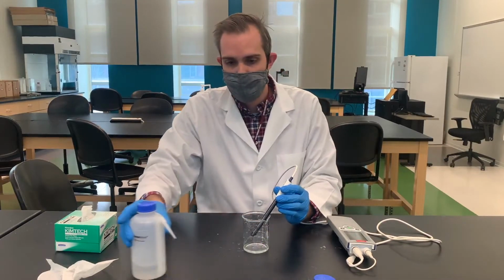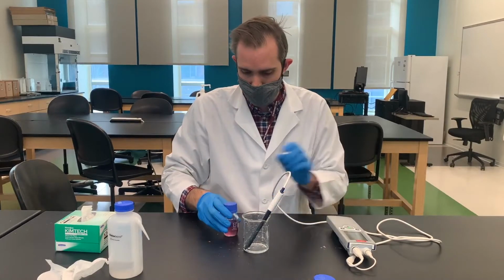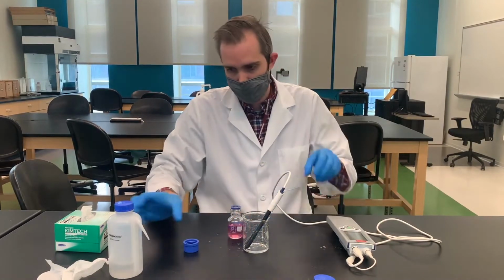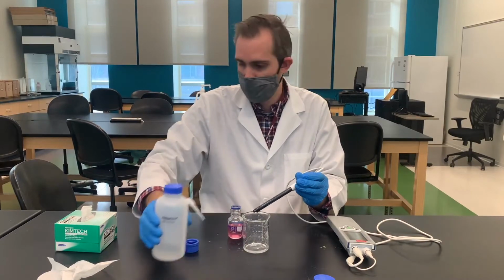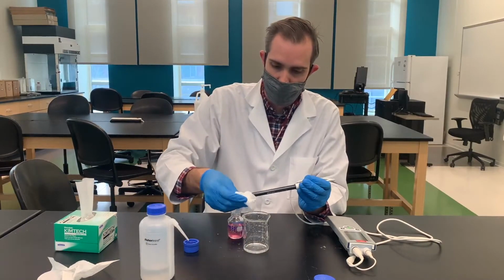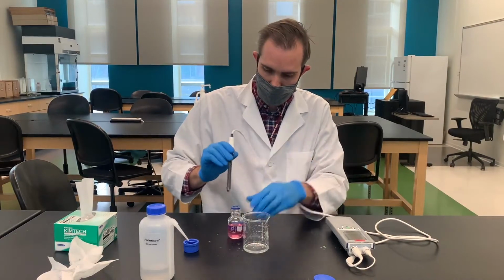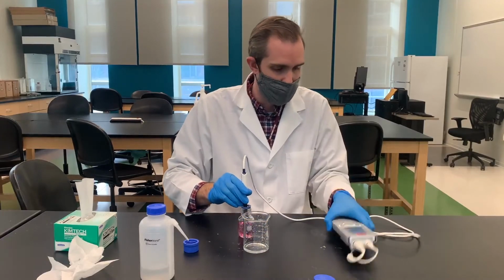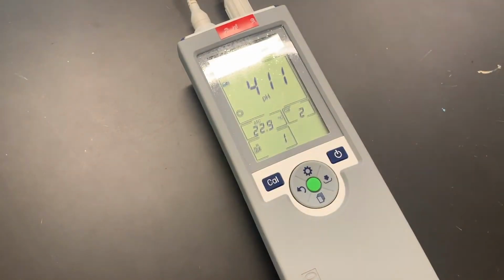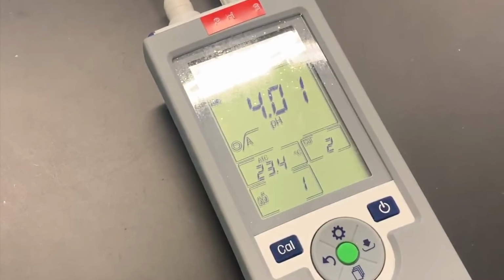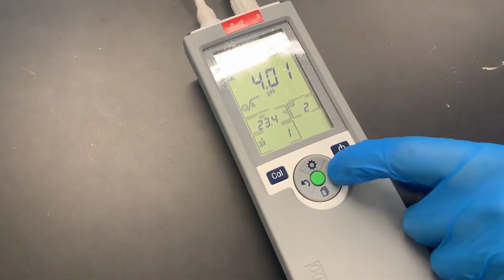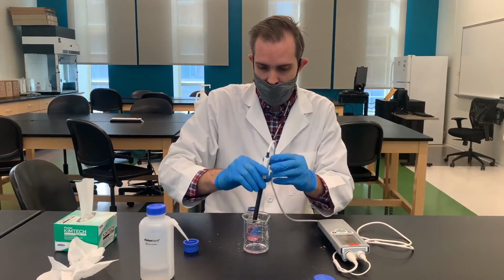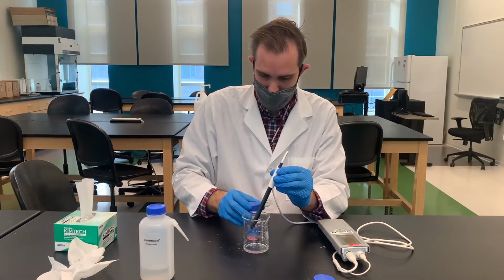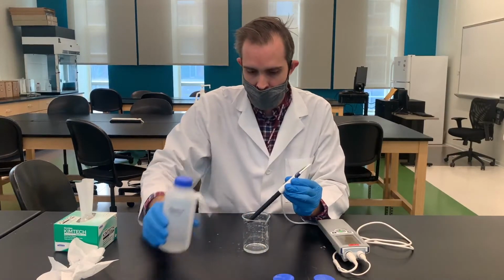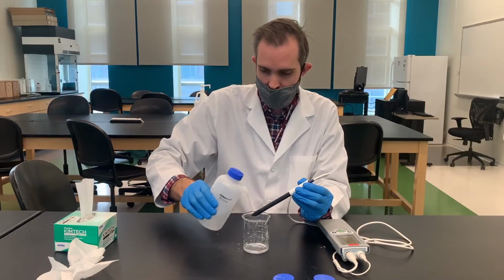Afterwards, you'll repeat this process with the pH of 4. You'll have to rinse off the pH probe and wipe it off with a chem wipe. Stir it around a little bit, and then you'll hit the calibrate button once again. The number on the bottom right of the probe should now say 2 because this is your second reading.